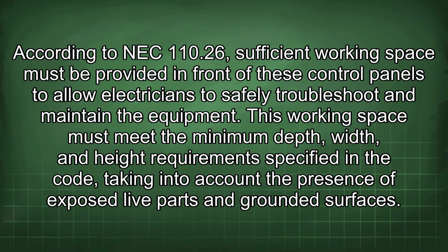According to NEC 110.26, sufficient working space must be provided in front of these control panels to allow electricians to safely troubleshoot and maintain the equipment. This working space must meet the minimum depth, width, and height requirements specified in the code, taking into account the presence of exposed live parts and grounded surfaces.